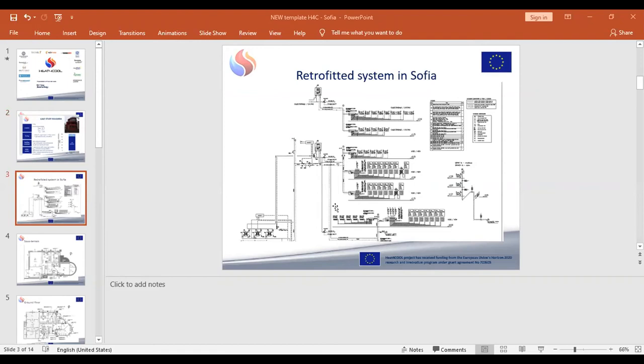The heating system consists of an electric heat pump, a phase change material (PCM) heat battery, and a photovoltaic system. A centralized heat pump system is chosen because of the high efficiency and lack of space inside the apartments to put a heat pump and boiler. The heat pump of 10 kilowatts provided by the geothermal company is directly connected to the PCM storage. The heated water is drained through a pipe system to 2 gas boilers.